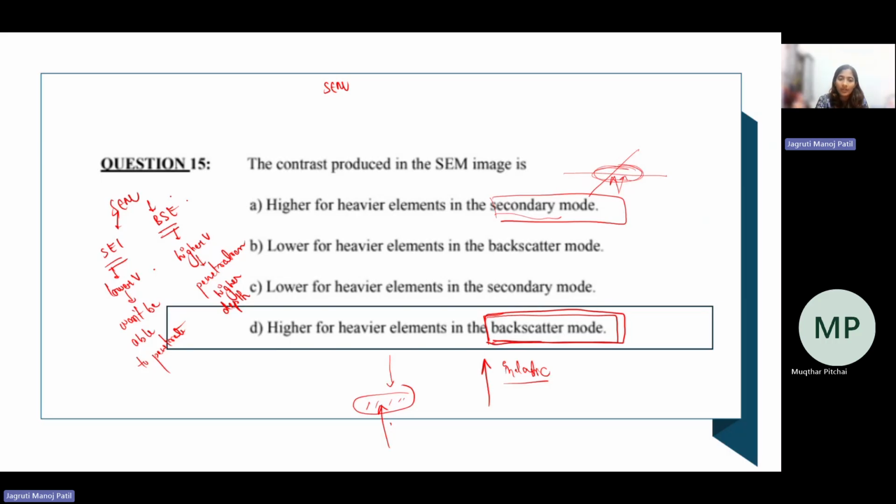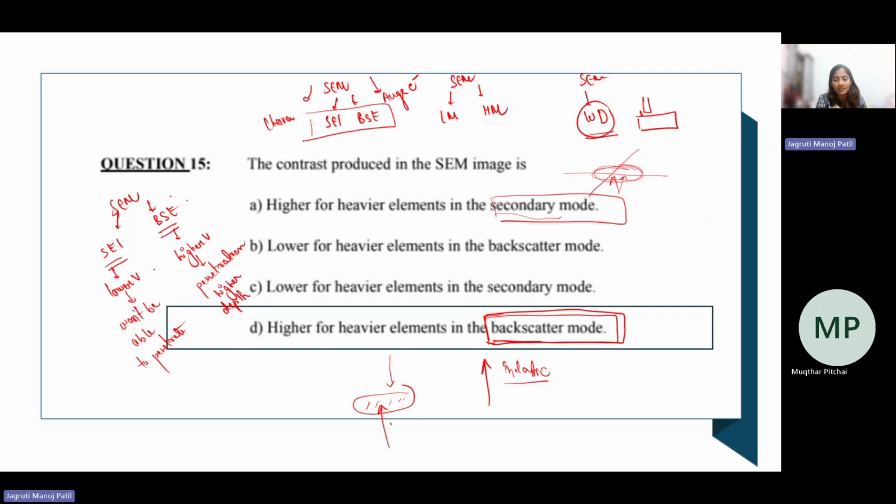If you have those kinds of detectors, of course you can make them. But the classical systems only come with secondary electron imaging and backscatter electron imaging. Based on that, we also have low magnification imaging and high magnification imaging. After that, you have your imaging characterized in terms of working distance, so how far the beam and the specimen are placed apart from each other. Based on the working distance, you also have image differences. Now, if you have multiple detectors, you can take an image from the characteristic X-rays, or from the Auger electrons, but if not, then the classical ones are only these two.